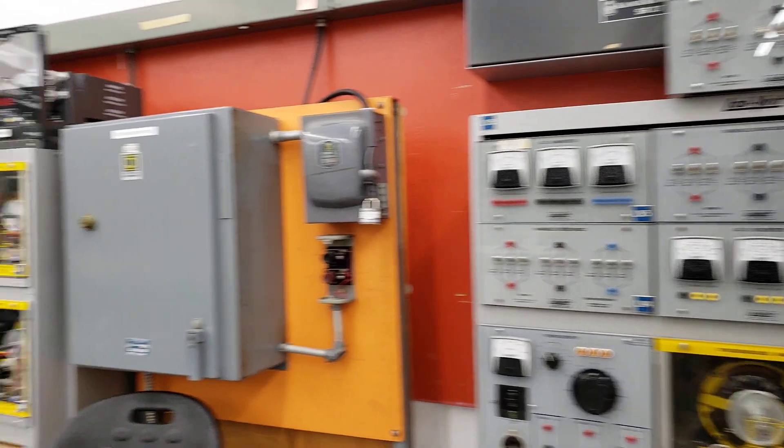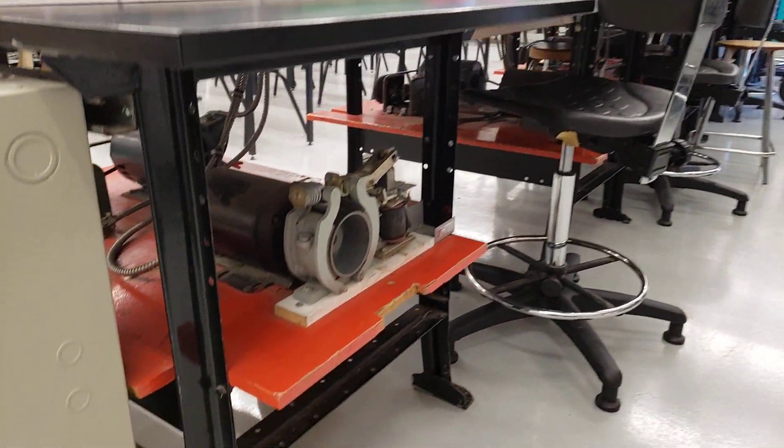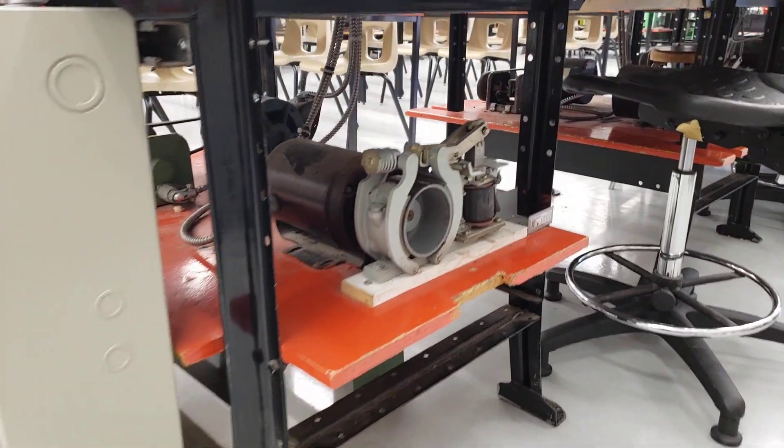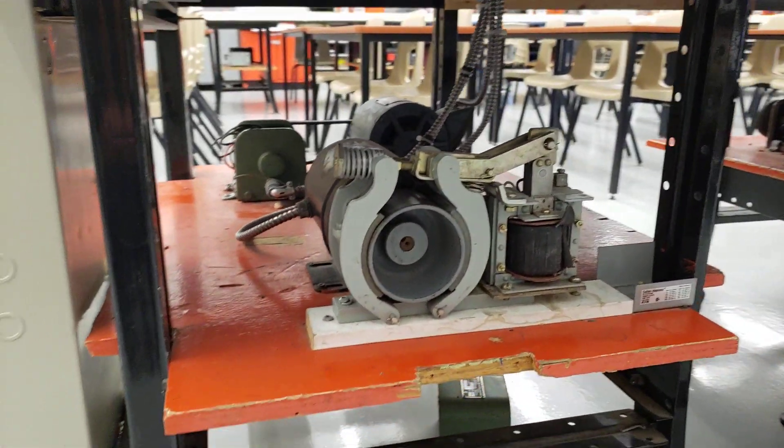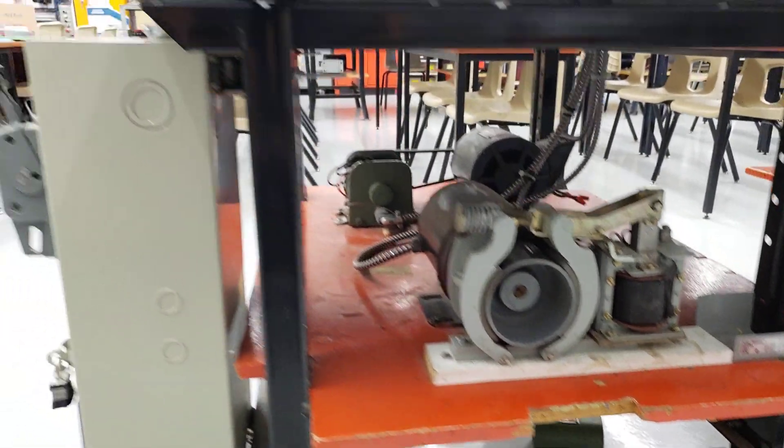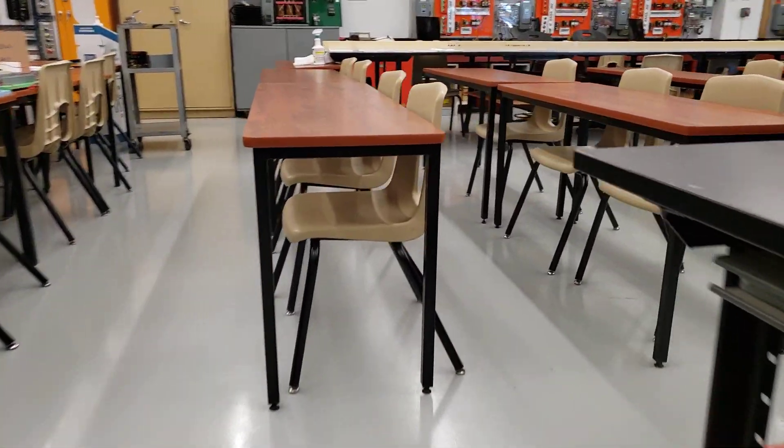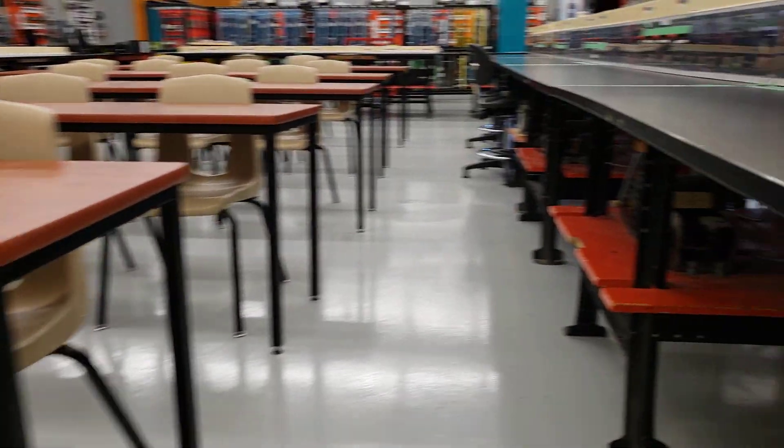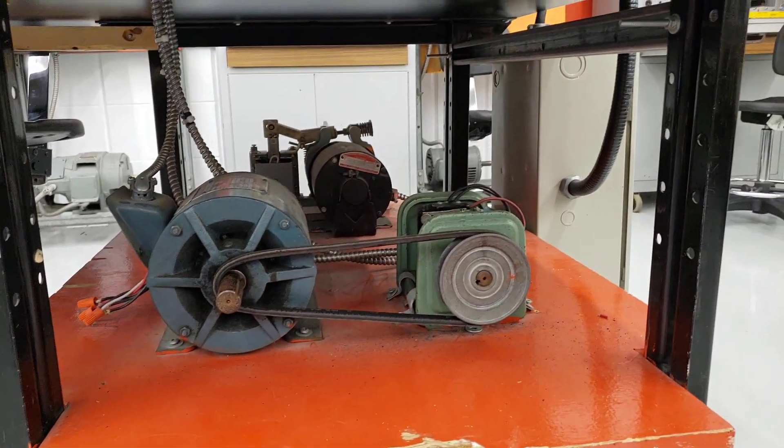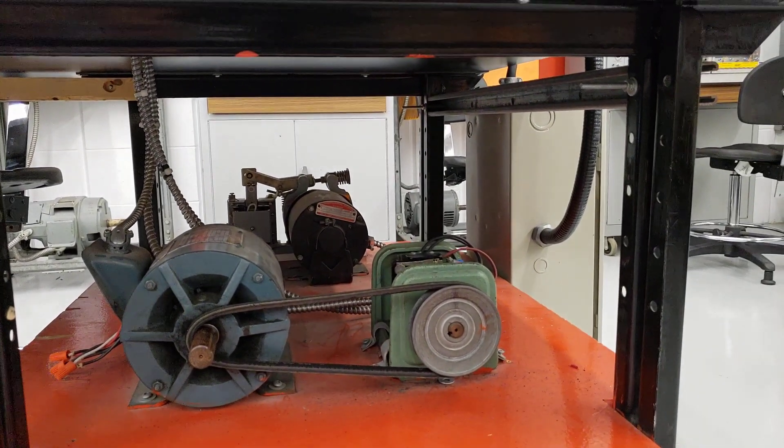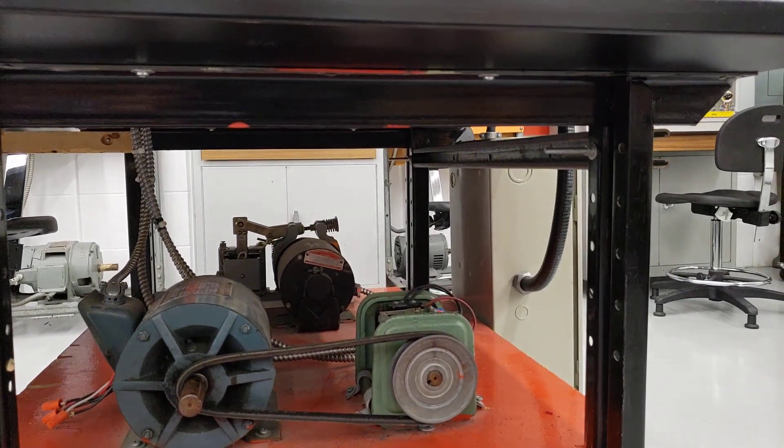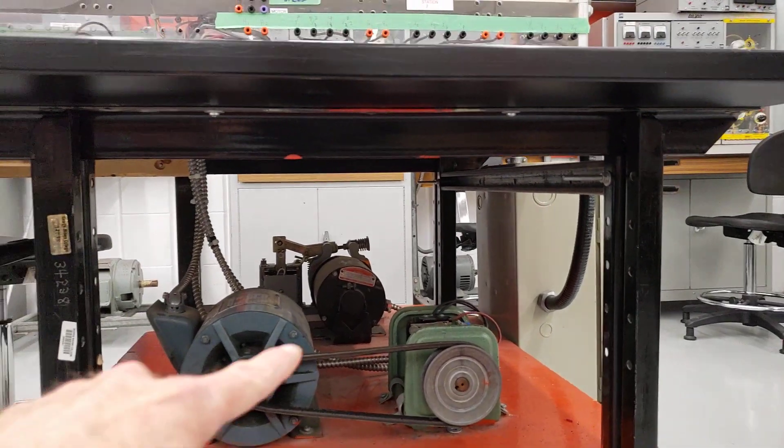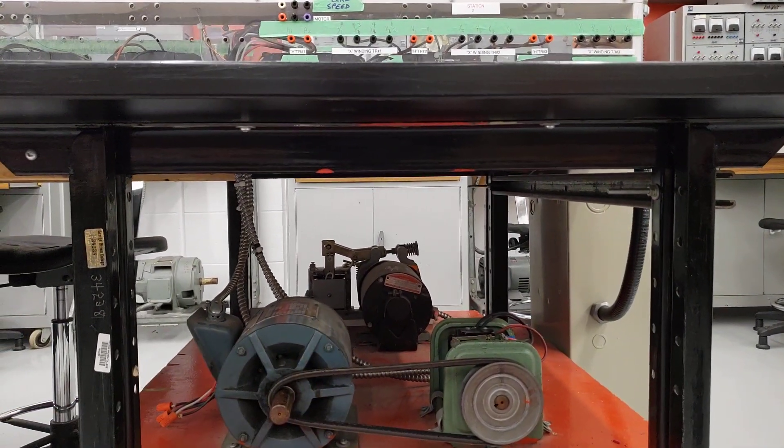In addition to those stations, you'll see that around the room, we have different braking systems. So this one here is a solenoid mechanical brake. We have another one on the other side, which is a plugging circuit. So we have a centrifugal switch here that then allows the motor to be run in reverse and stop the motor on a dime versus the mechanical brake that we see on the other side there.